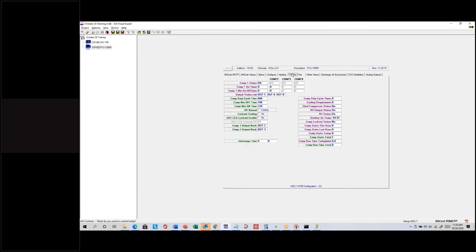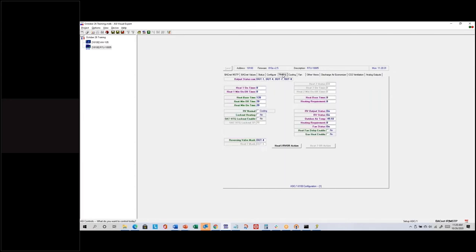For a heat pump, the timing settings for the compressor — whether for heating or cooling — are set on the cooling tab. The heating tab for heat pump cases only applies to that extra stage of auxiliary heat, if you have one more stage of heating compared to cooling.